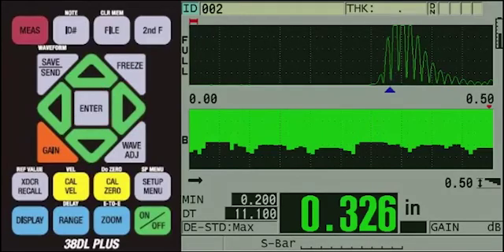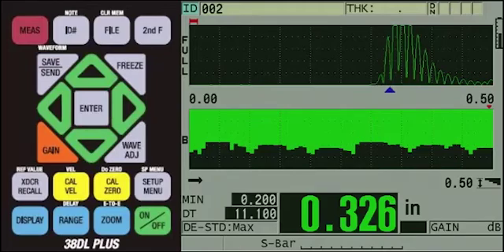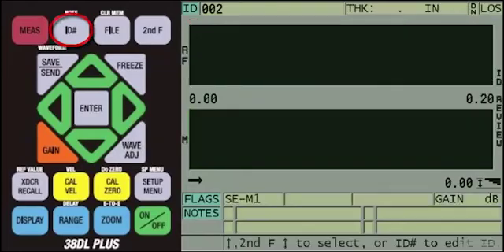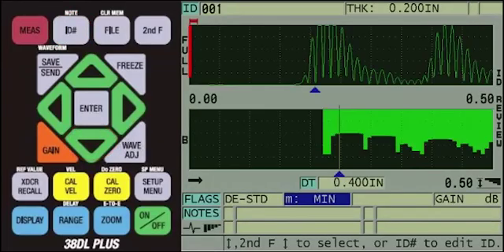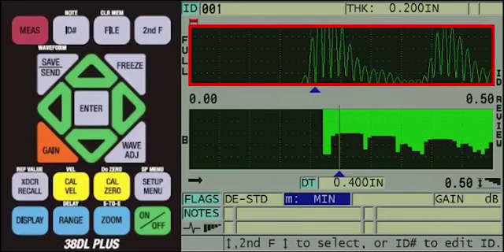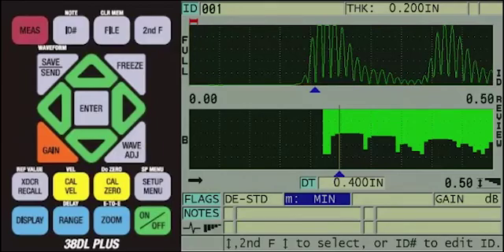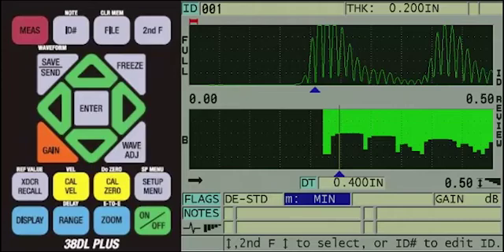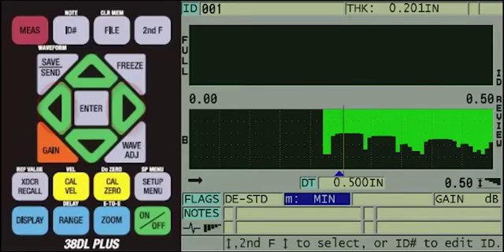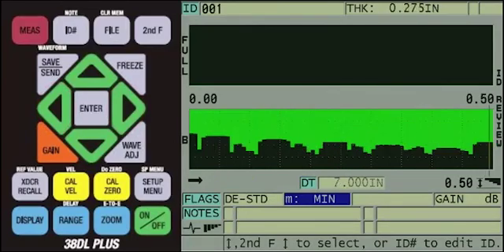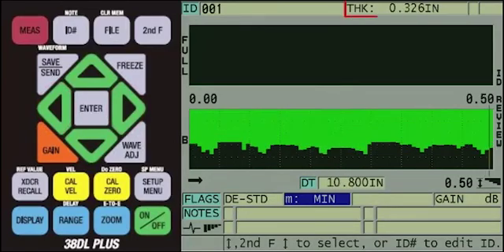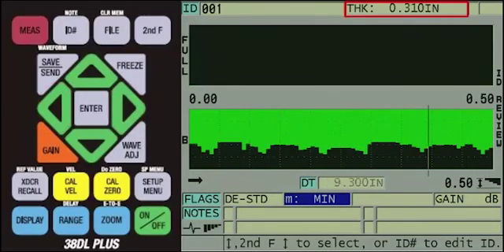If you want to review the saved scan, you can press the ID number sign key, and then press the down arrow to ID 001. The gauge displays the A-scan it saved, which in this case corresponds to the minimum thickness reading. The user can press the second F key, followed by the left or right arrow key, to quickly jump to the next full B-Scan screen, and also use the left and right arrows to review the individual thickness readings within the B-Scan. Once again, the thickness at that spot is displayed along with the distance traveled by the buggy to get to that spot.